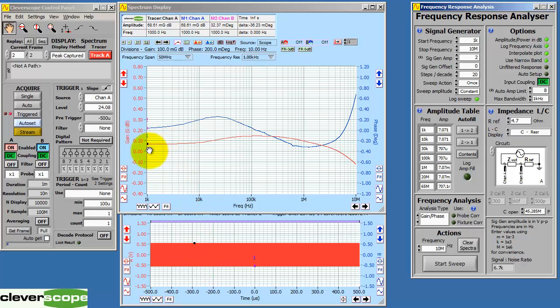As you can see, we've got a gain variation of about plus or minus 0.1 dB. That's not too bad. Phase is varying between minus 0.3 and plus 0.6 degrees. Also quite reasonable. But if you want to get best accuracy out of your component measurements or the flattest gain phase response, you can use the calibrate probes analysis type. We start again by going start sweep.